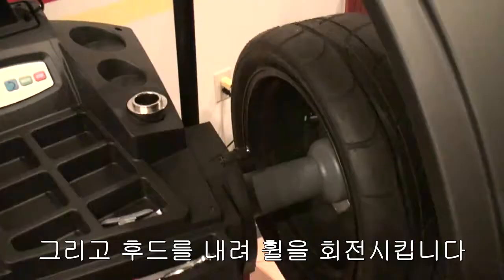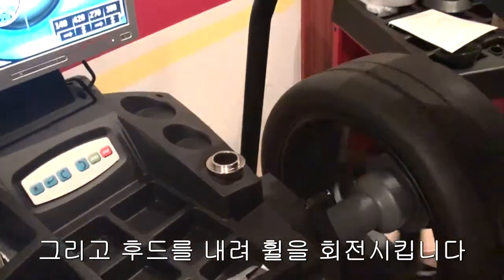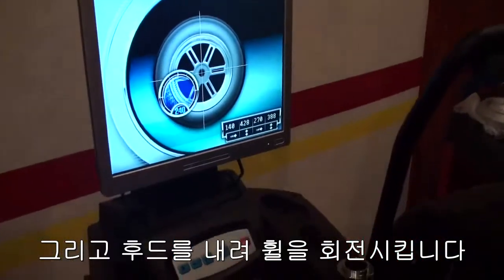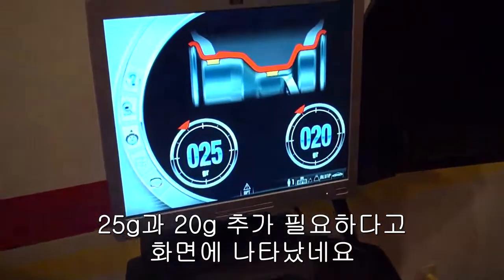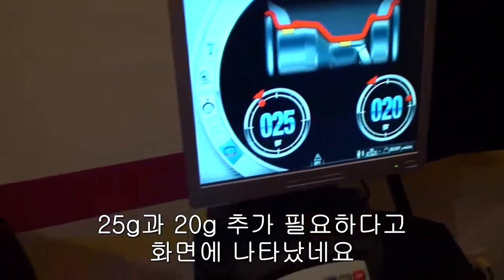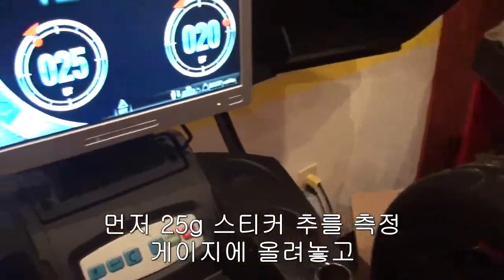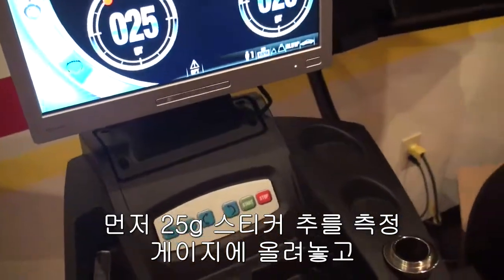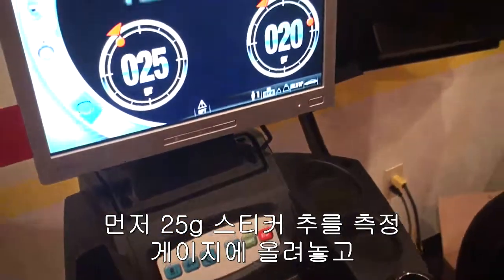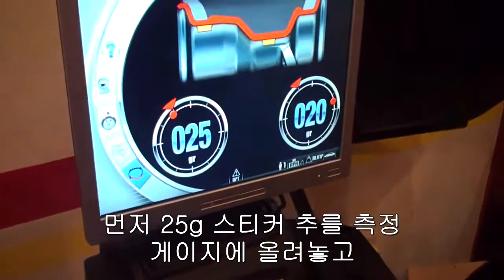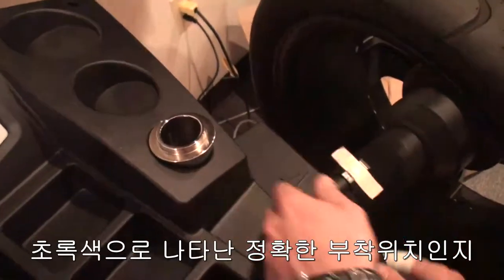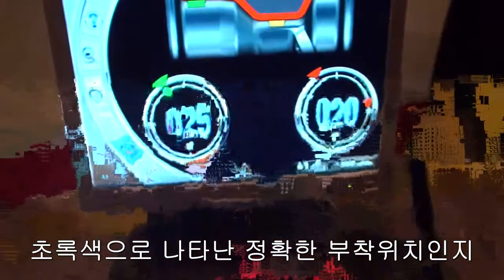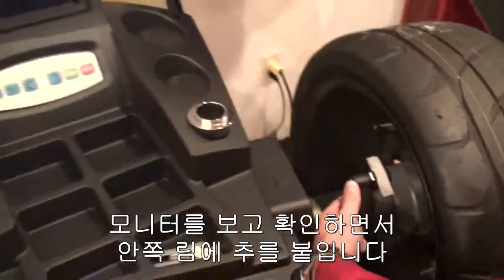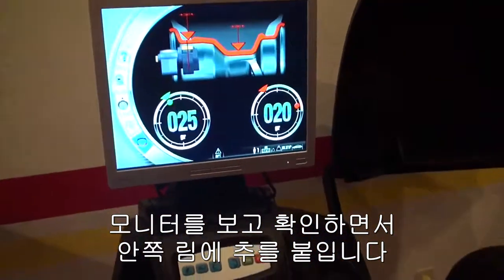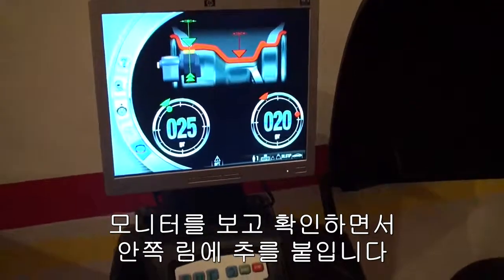Just take the hood down now and quickly perform a spin. You can see it's ready to go. We have 25 grams and 20 grams. So I just take my sticky weights, 20 and 25. Place the 25 grams on this gauge. Make sure we stop in the correct position. And as you can see, it tells me green on the internal one. And now by taking out my gauge and looking at the monitor, you can see when I reach the right spot. The arrow will become green and tells me this is the right spot.